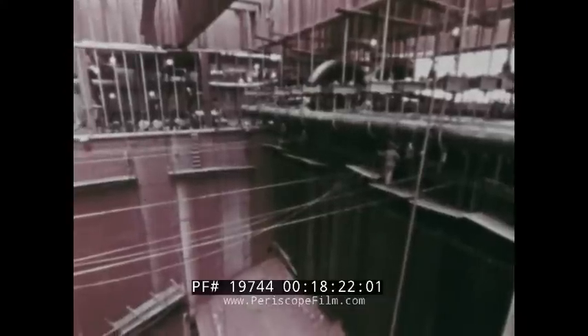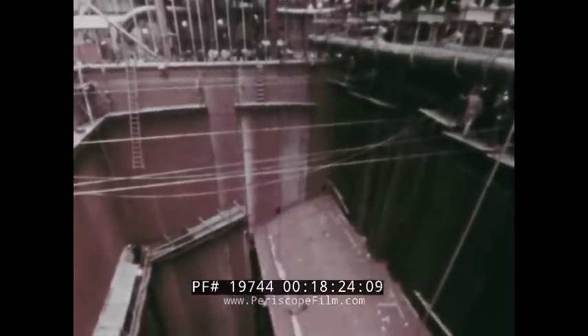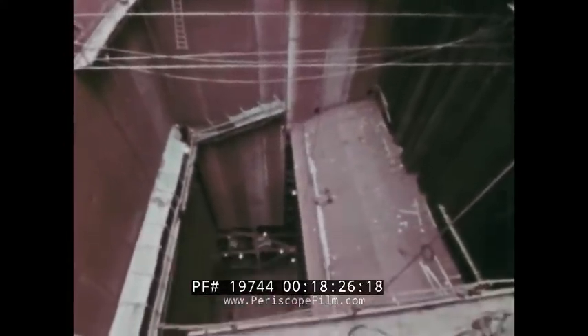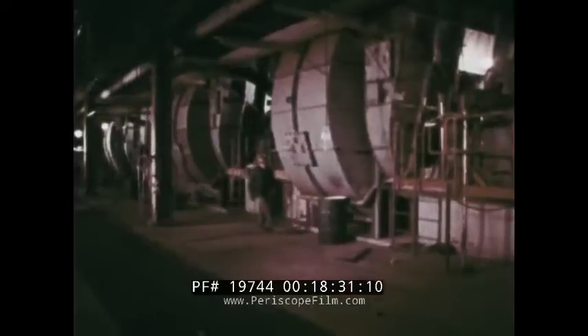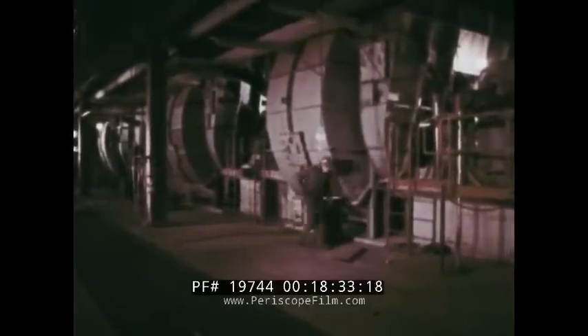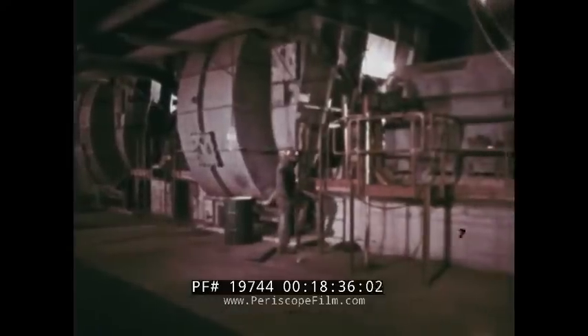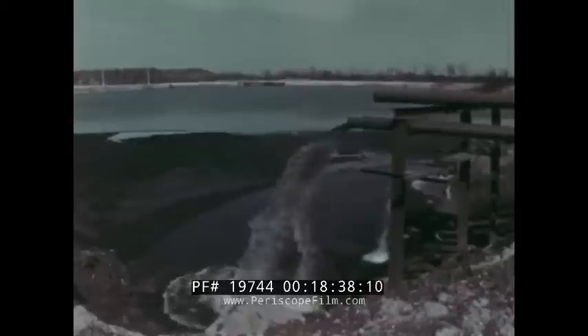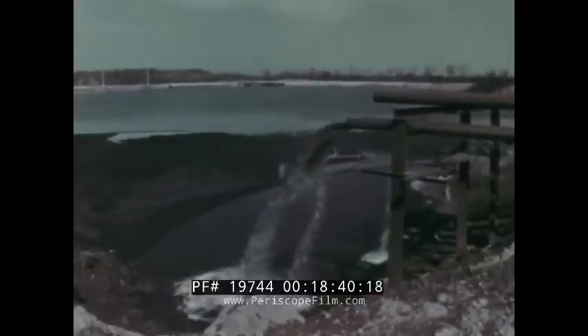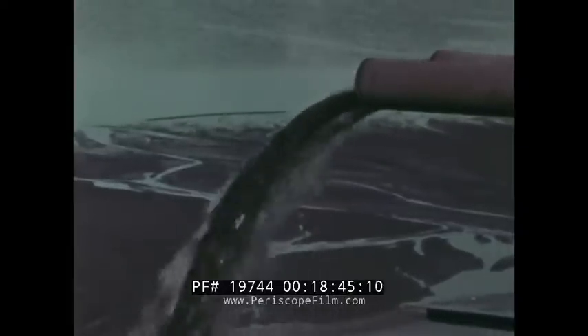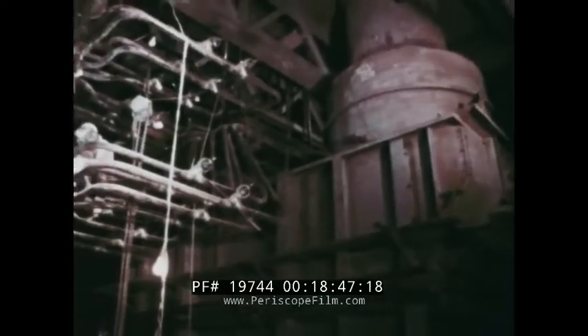TVA used cyclone-fired furnaces for the first time at Paradise. Powerful fans provide the cyclone force of hot air, which mixes with the crushed coal within the 14 burners where the combustion takes place. The temperature reaches 2,800 degrees. The molten ash is sluiced hydraulically from slag tanks to large settling ponds. Boiler erection required more man-hours of skilled labor than any other single feature of construction.